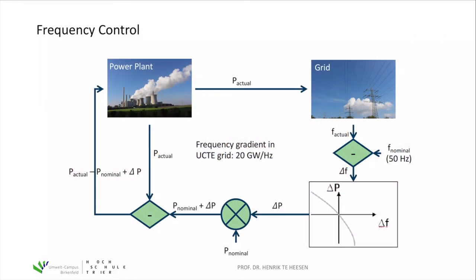One major service provided by energy utilities and grid operators is frequency control. Our AC grid has a nominal frequency of 50 Hz, and operators must set up their power plants' actual output to achieve this frequency. In case of any small deviation, the actual power must be adjusted to restore the nominal frequency. The power plant generates actual electric power fed into the grid, producing an actual frequency which is compared to the nominal 50 Hz.